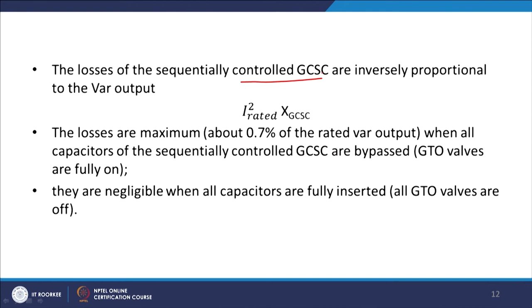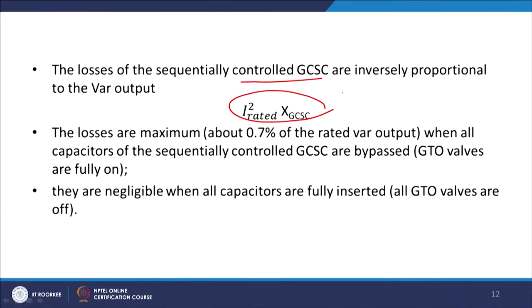The losses of the sequentially controlled GCSC are inversely proportional to the VAR output, since it is a current-dependent device. The loss is I² × X_GCSC. The loss is maximum — about 0.7 percent of rated VAR output — when all capacitors of the sequentially controlled GCSCs are bypassed and the GTOs are fully on. Losses are negligible when all capacitors are fully inserted and all GTOs are off.